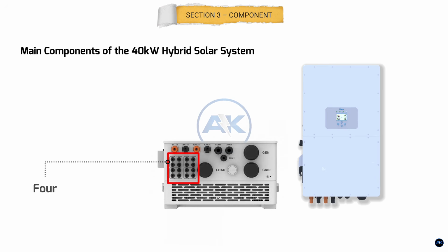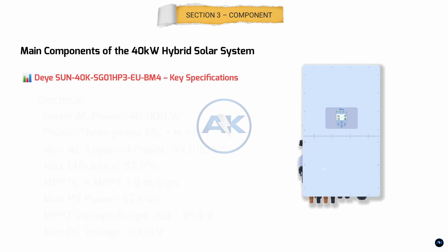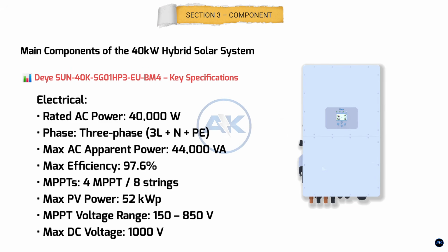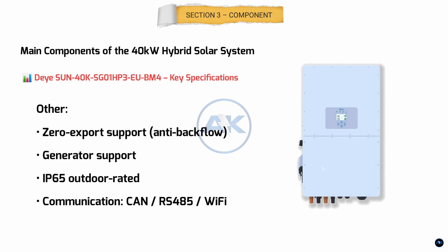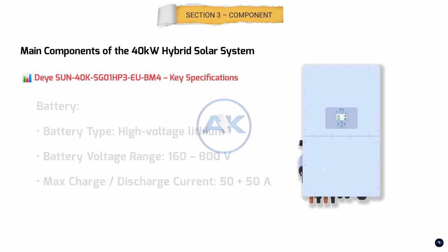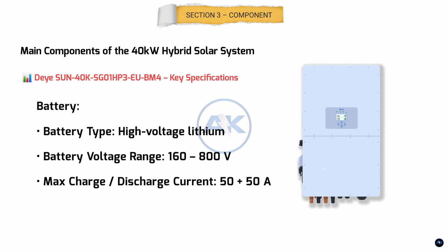It features 4 independent MPPTs, allowing multiple solar strings to be connected while maintaining high efficiency and flexible system design. The inverter delivers 40 kilowatts of 3-phase AC power and supports both grid-connected and backup operation. Because this project requires zero export, the inverter will be configured so that no excess solar power is fed back into the utility grid. The Deye inverter also supports high-voltage lithium batteries, generator input, remote monitoring, and advanced protection features, making it suitable for commercial installations.